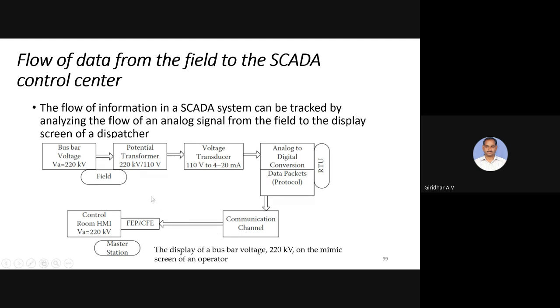Where the field communication front end receives this data and passes it on to the control room. There you can see the servers and everything. A particular data will pass to particular servers; those things we can also see. So this is the typical way a bus bar voltage is mimicked at the SCADA center, the voltage state measurement.